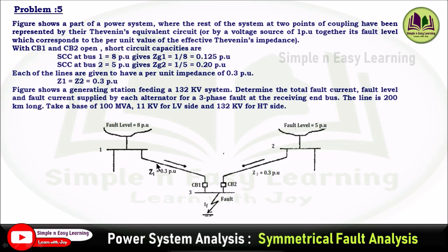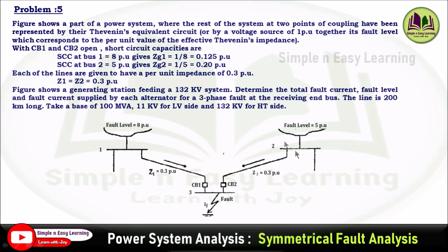This is a simplified diagram of a 3-bus system: bus 1, bus 2, and bus 3. The fault occurs at bus 3. Bus 1 and bus 2 are the generator buses with fault levels of 8 per unit and 5 per unit respectively. From bus 1 to bus 3 there is a line with impedance 0.3 per unit, and from bus 2 to bus 3 there is also a line with impedance 0.3 per unit. We need to determine the fault current, fault level, and fault current supplied by each generator.